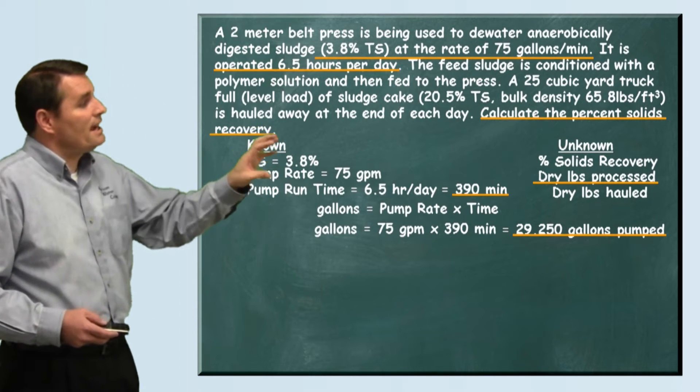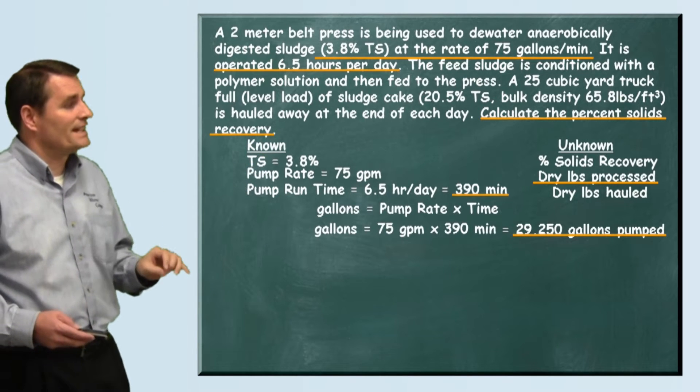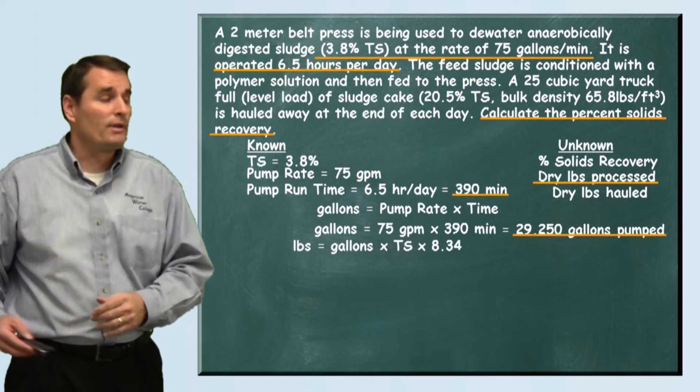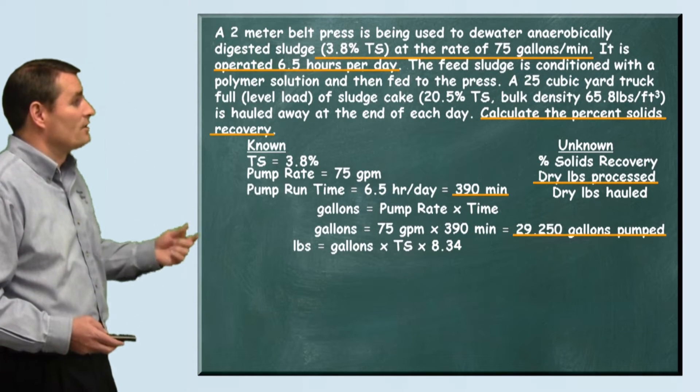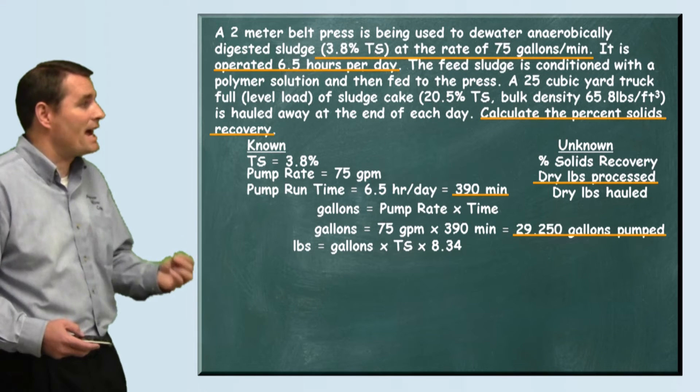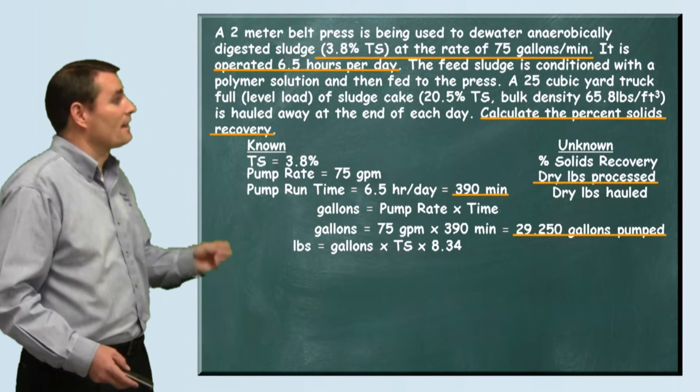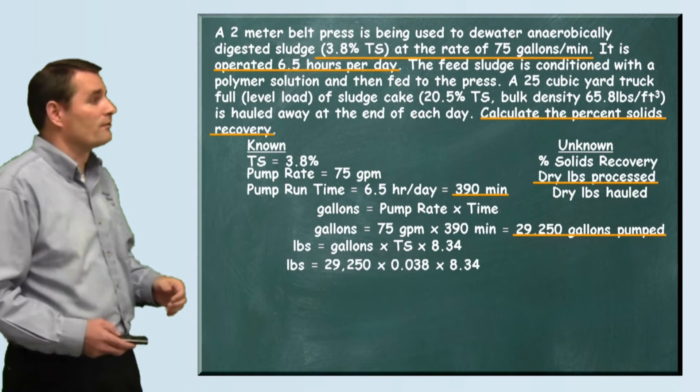We can take our 29,250 gallons and now calculate how many pounds of dry sludge are being processed. We do that by using our formula that says pounds equals our gallons pumped times the total solids times 8.34.